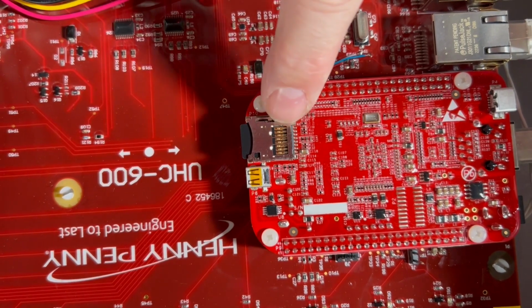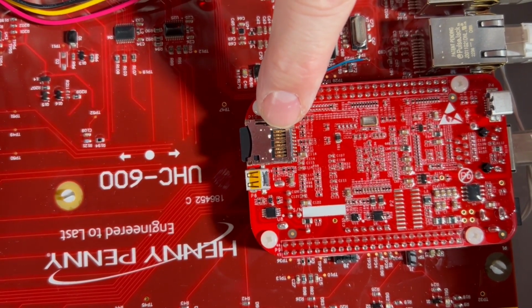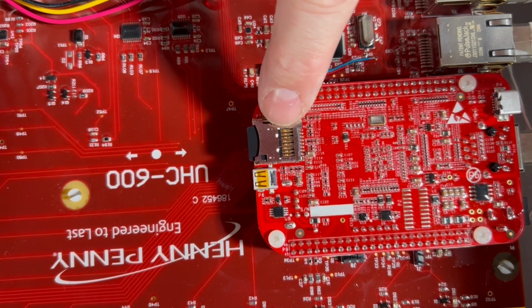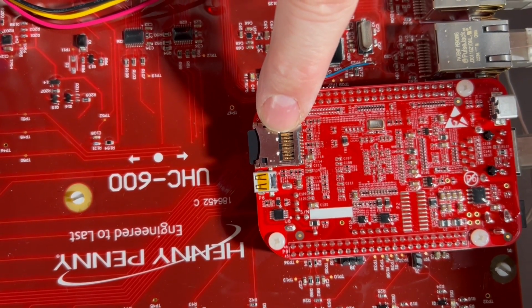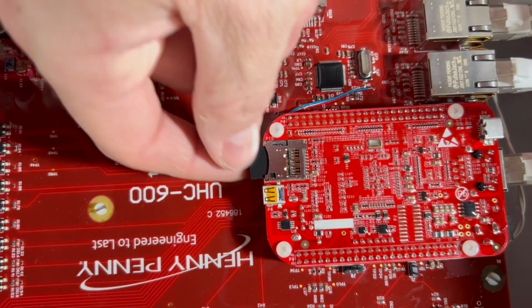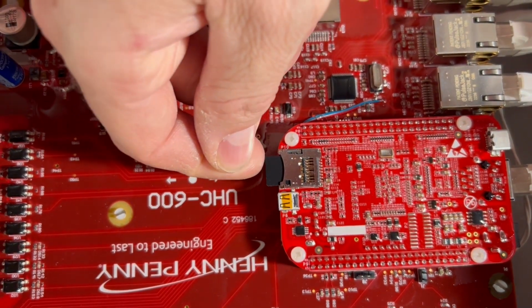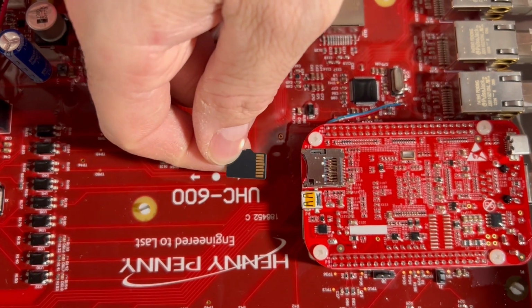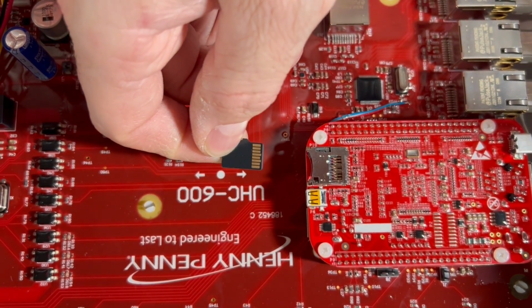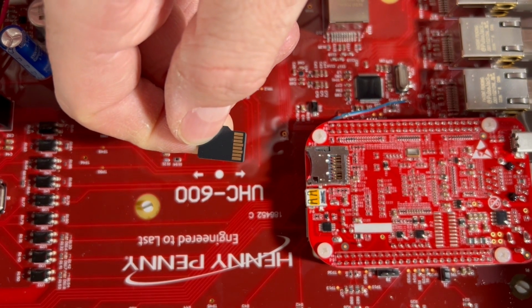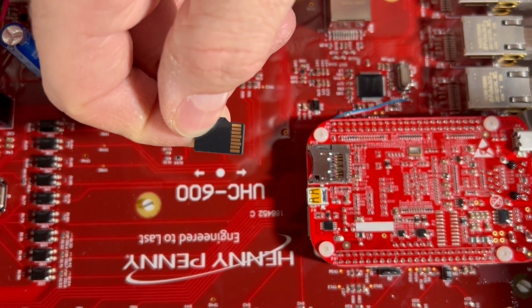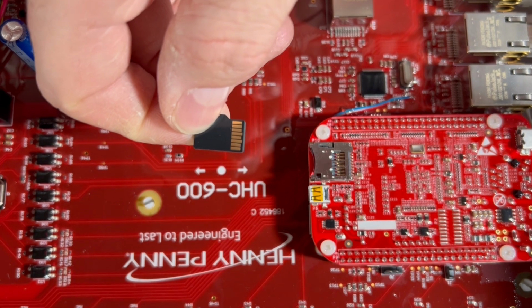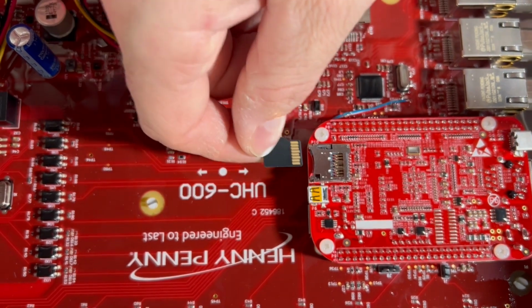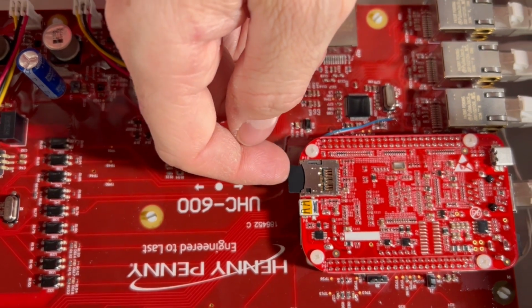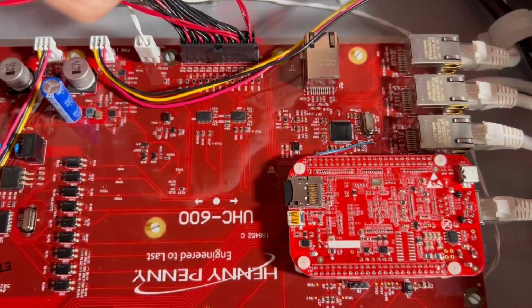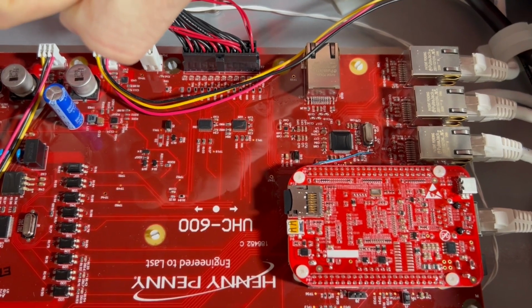Right here we can see our SD card located on top of our I/O board, and the troubleshooting we want to do is make sure the unit is powered completely down. We're going to want to remove that SD card, and you can see when I pushed in on it, it was spring loaded and popped out. This is where we can pull it out and clean these contacts you can see on the SD card. We want to be very careful cleaning those, making sure we don't mess them up, and then reinsert the SD card back into the slot. We can power the unit back up and see if that resolves the error.